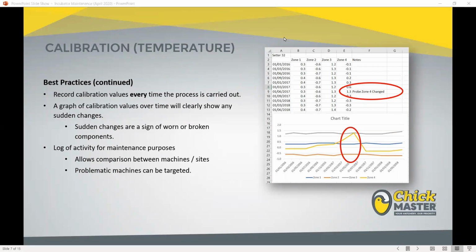Okay. And when you calibrate, you're in effect putting in the wrong temperature reading. So by pulling those relays off and disabling the heating and the cooling, your temperature in the cabinet will gradually decrease, but that's absolutely fine. And it's on a very slow decrease. So it's something that you can manage through the calibration process.